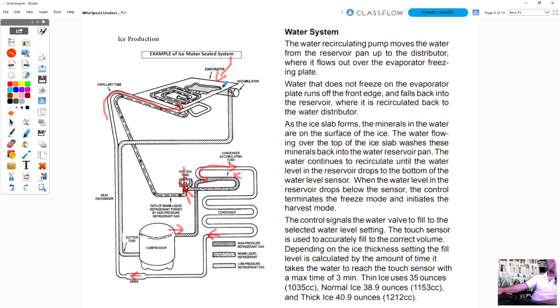And as water flows over it, it freezes, and then it comes back down through our suction line right here. Notice we have another accumulator on our evaporator, because as we're producing ice, the water that's flowing over the evaporator is providing heat to cause the refrigerant to vaporize. So as the ice starts to build up, there's less heat on the evaporator. So again, we're using an accumulator here to prevent liquid refrigerant coming back during the cooling cycle. The condenser accumulator is to prevent liquid refrigerant from coming back during the ice ejection cycle. So this water is constantly flowing over the evaporator and circulating until it builds up ice.